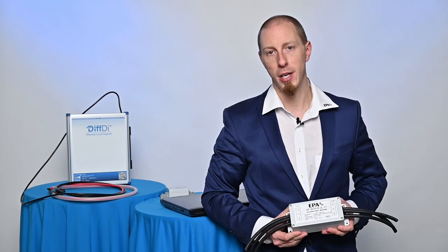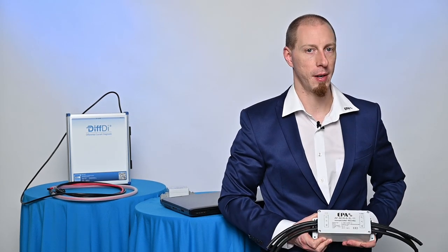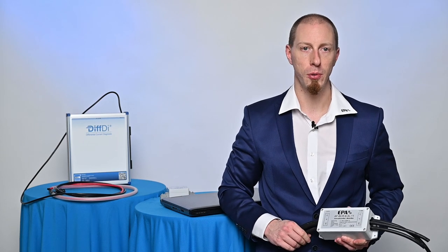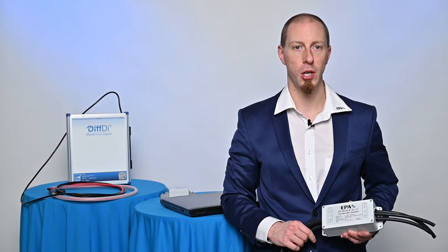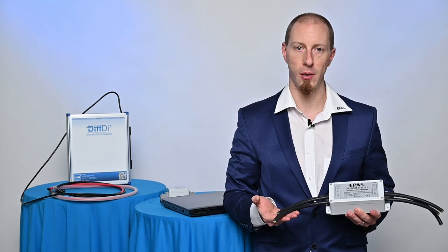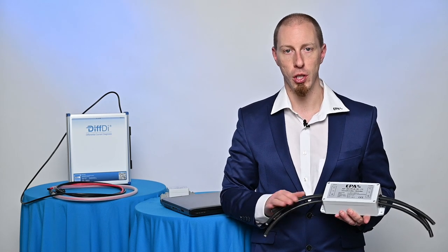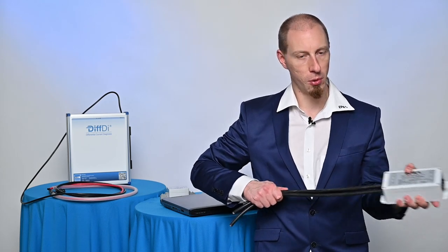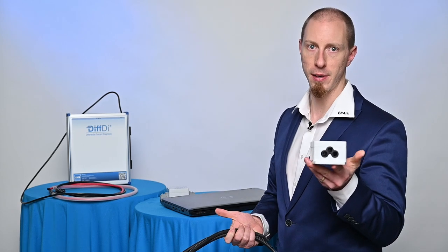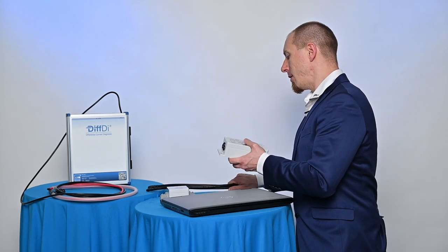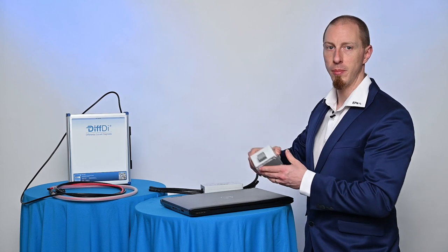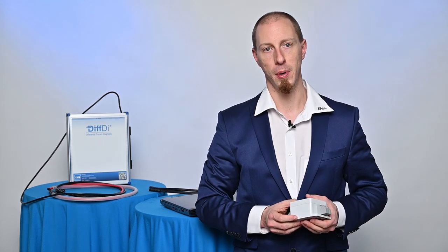The design and the installation of the BCR filters are extremely simple. The completely encapsulated plastic housing is screwed onto the mounting plate, and the three wires of the frequency inverter output are simply fed through the absorption tunnel of the filter without any screw connections. That's all. For special applications with low rated currents, models with terminals are also available.